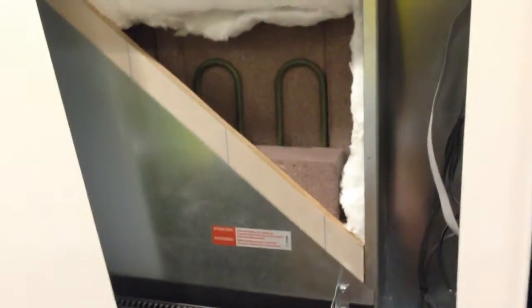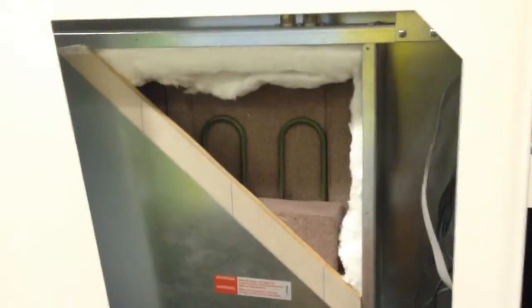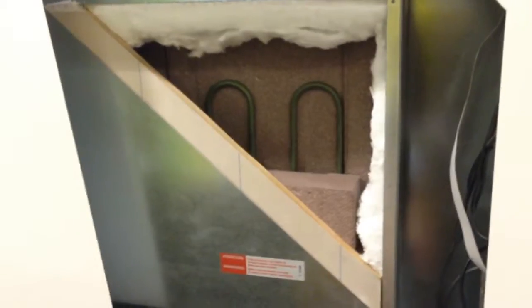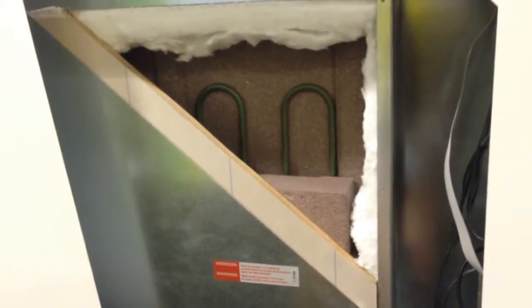We're going to take a little look since we've got this cutaway unit here, and I wanted to give an explanation on how these work. These function in two capacities. The primary purpose is as a storage heater. In here you can see these electrical elements and these bricks, which are ceramic — we're missing a couple here for demonstration purposes.